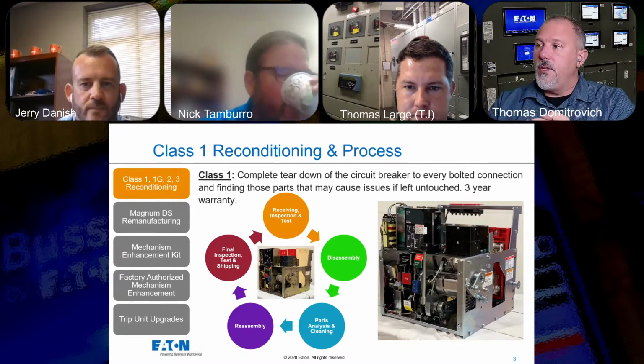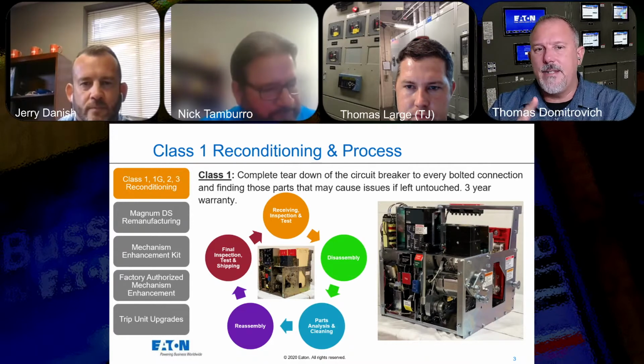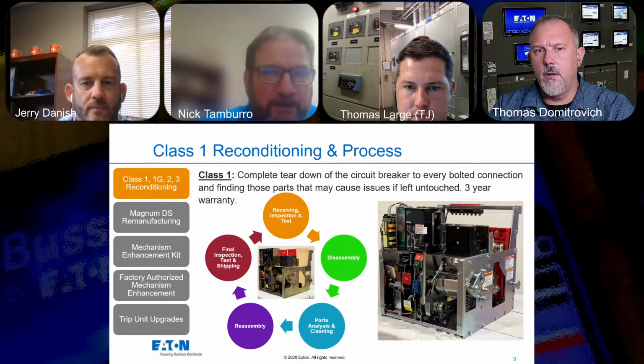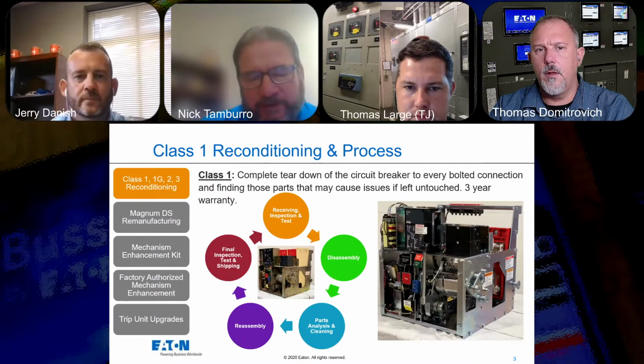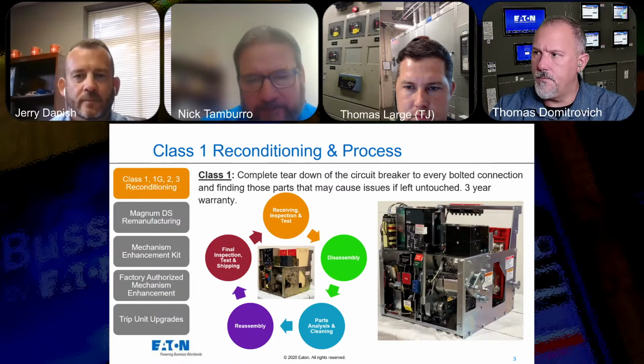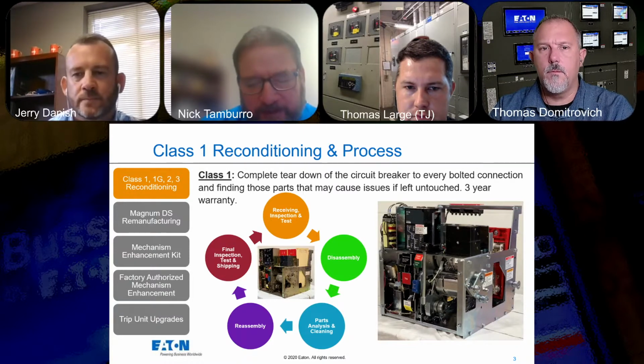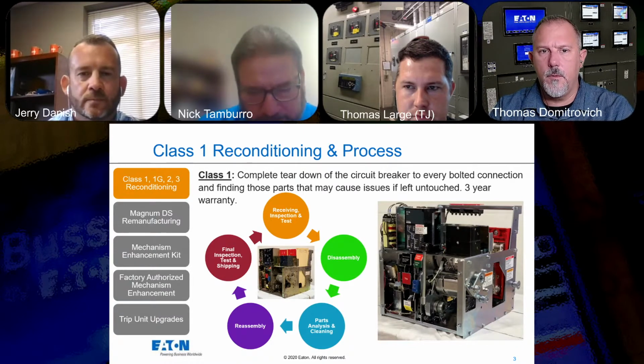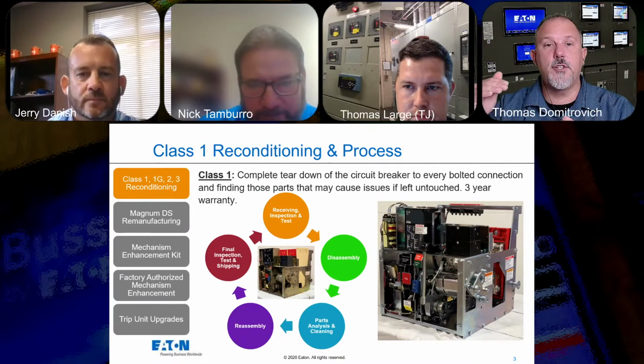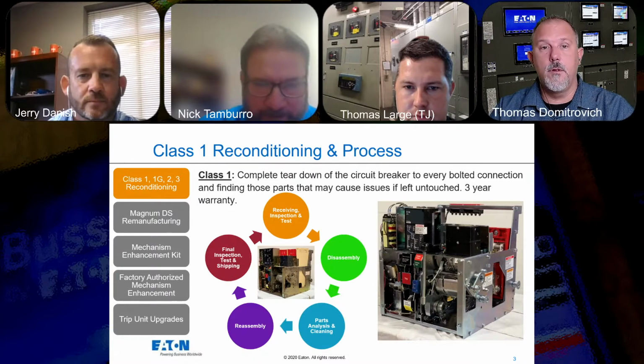So you said 5 times and 10 times? No, we do 5 open, 5 close. So you're operating and charging it each time. We do the same thing on outgoing, at rated voltage and min max. So 5 min, 5 rated, 5 max, so it'd be like 15. When you say min max, you're talking about min and max voltage? Yes. Some equipment is rated 85% minimum.